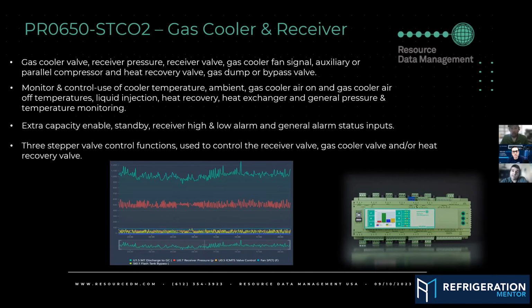A lot of times, I think, just by the nature of how things get ordered from OEMs, they'll have a rack with a rack controller, and then they have like a glycol loop heat reclaim system, and they don't use our heat reclaim on the rack controller. They'll actually use our TDB and write their own program. And I think that's just by nature of how things are ordered and kind of logistics there. But you can do heat reclaim with these controllers. So with this one control, your one STCO2 controller, you can do 3 valves off that. You don't need an auxiliary pack or anything like that. Correct. Or module, sorry. Okay.